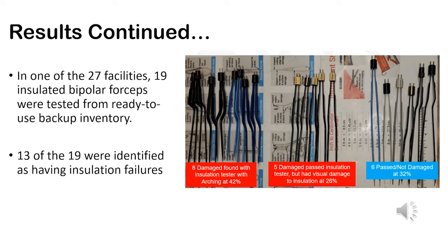In one of the 27 facilities, 19 insulated bipolar forceps were tested from ready-to-use backup inventory. 13 of the 19 were identified as having insulation failures. 8 damaged insulation forceps came out to 42% with arcing. 5 were damaged. They passed the insulation tester, but had visual damage to the insulation itself at 26%. And then 6 passed with no damage at 32%.